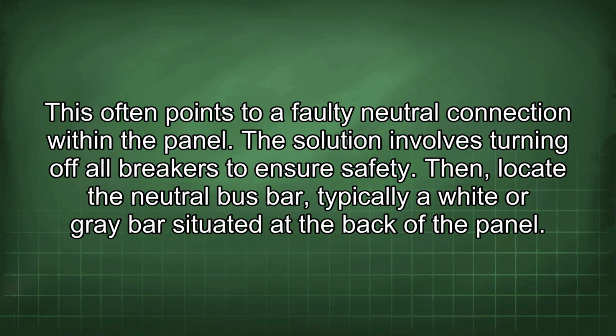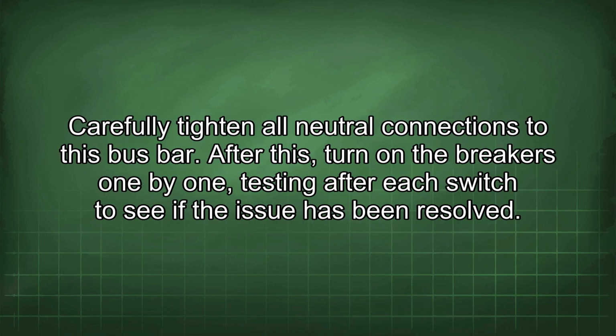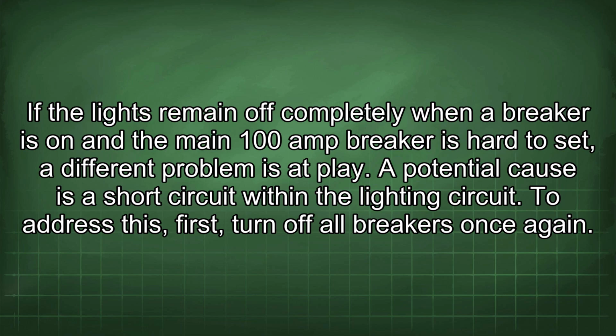The solution involves turning off all breakers to ensure safety. Then, locate the neutral bus bar, typically a white or grey bar situated at the back of the panel. Carefully tighten all neutral connections to this bus bar. After this, turn on the breakers one by one, testing after each switch to see if the issue has been resolved.